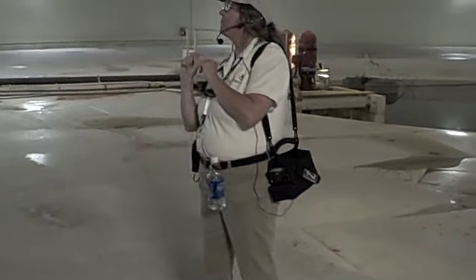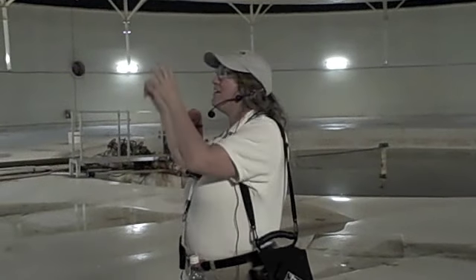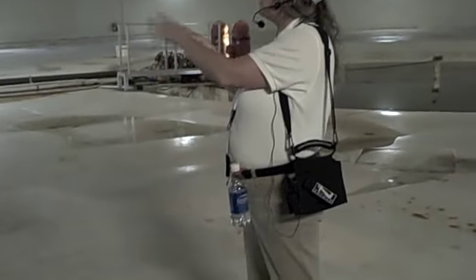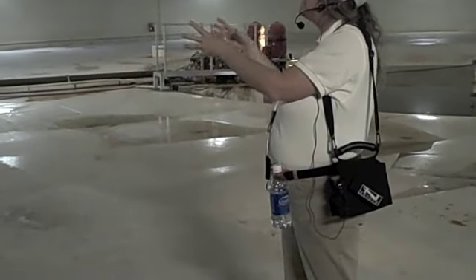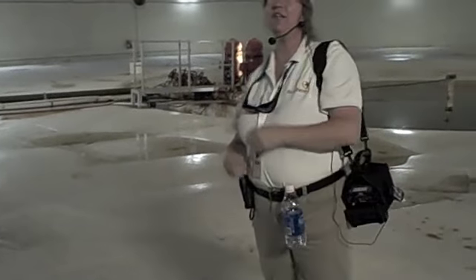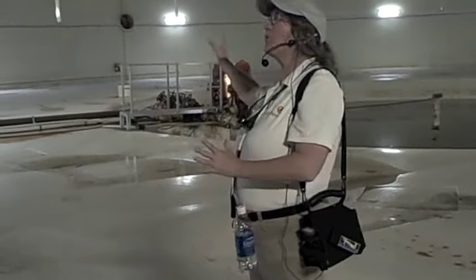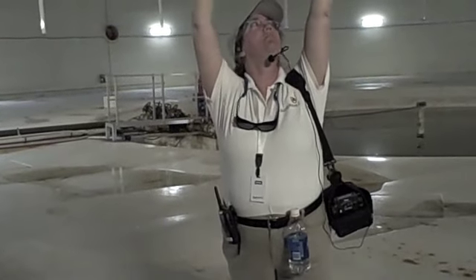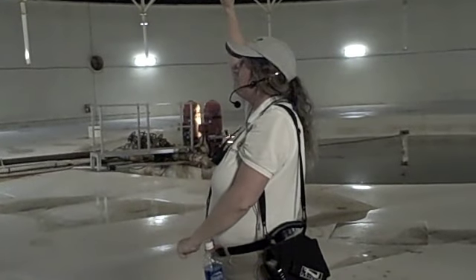And the reason why we needed an expanding and contracting room is because the sunlight is coming into the glass portion of the biosphere, which is sealed, and the air inside of that is expanding. The air needed an escape route. It comes down the tunnel into this room and pushes up on the hypalon, on the diaphragm, and it makes that go up and expands the volume of the room.